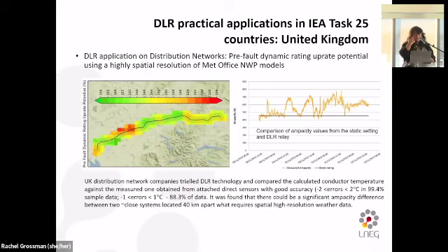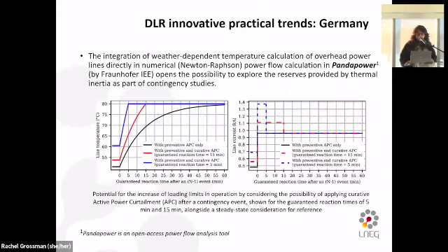This is an example from the United Kingdom. Again, in the same situation, they use a methodology very similar to the one we applied in Portugal, with the identification of critical points that limit the capacity of the grid. It's a simpler graphic, but comparing the dynamic capability obtained with our method, the applied methodology, and the static rating, they can also ensure extra capacity almost 100% of the time.